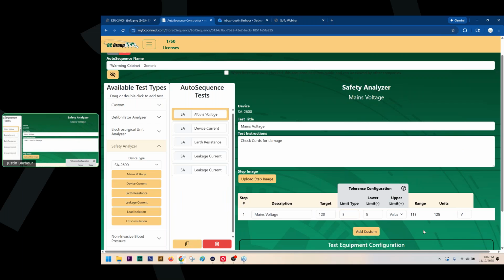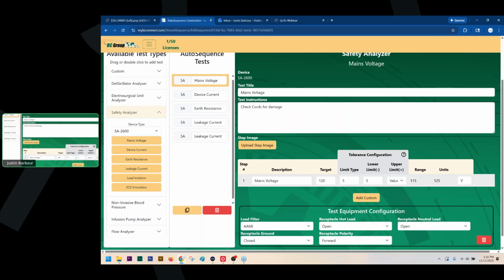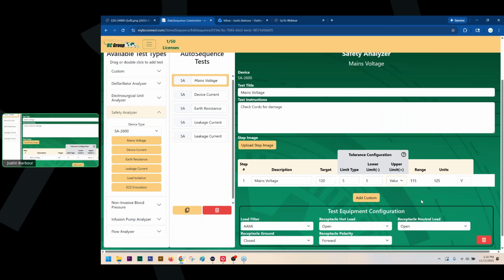So in this case, we should see 120 volts, but as long as our automated electrical safety analyzer falls between 115 and 125 volts, you'll get a passing condition on the step. This is where the magic is—you can adjust your values and set limits either by percentage or by a specific value. I myself love specific values, because percentages can be too loose. Like ESUs, they say plus or minus 20%—that's a lot. I'd rather put plus or minus 20 watts or 10 watts. You can always go more strict than the OEM standard.